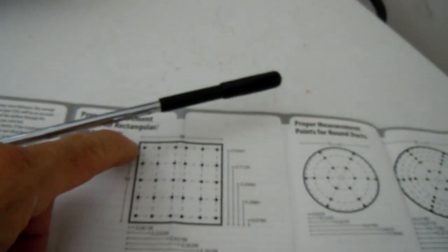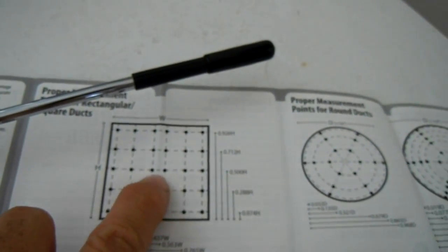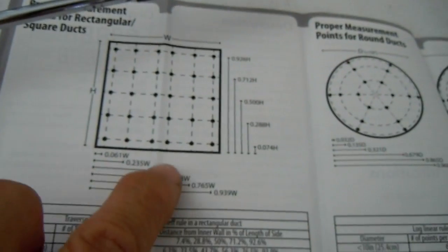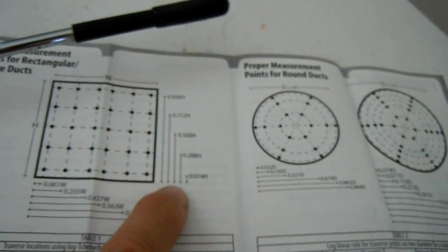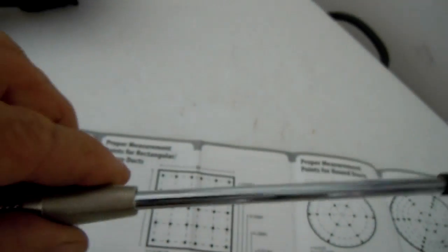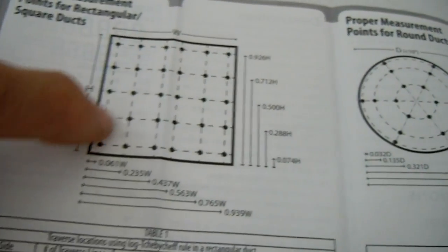Another factor that could easily throw off your readings is how deep your probe is into the duct. It really does matter big time. If you just kind of play around with inserting this into your duct, you'll get all kind of weird readings at different depths. It kind of gives you like a scale right here for square duct and another one here for round duct.